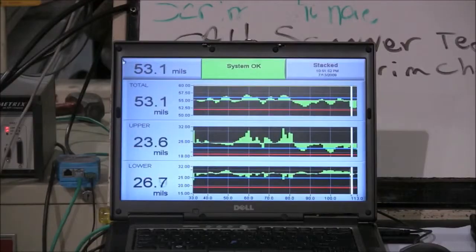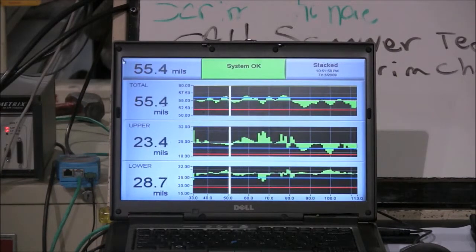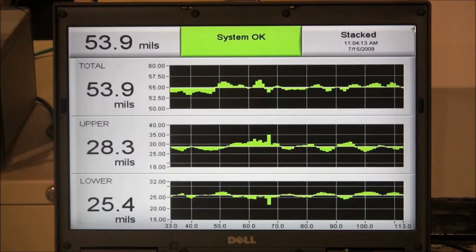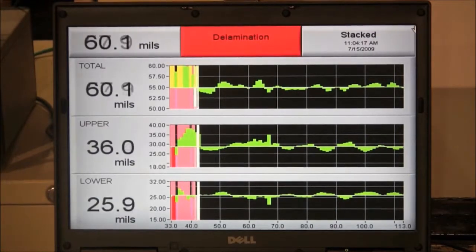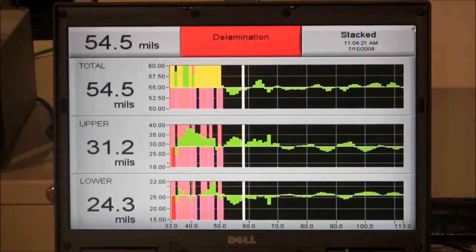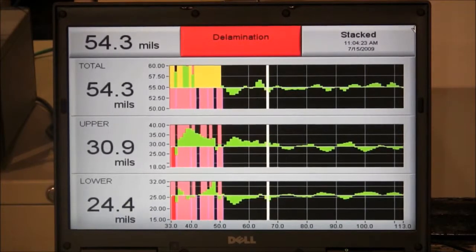The line operators monitor screens showing all three measurements to determine product quality. Each measurement is shown as a deviation from the average thickness. Limits are set to provide instant feedback if any layer of the sheet exceeds its tolerance. Highlighting on the background of the screen indicates delamination and allows the operator to adjust the process to minimize waste and save production costs.